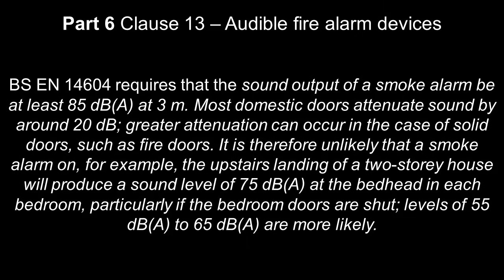That's the requirement. Most domestic doors attenuate sound by around 20 dB. Greater attenuation can occur in the case of solid doors such as fire doors. It is therefore unlikely that a smoke alarm on, for example, the upstairs landing of a 2-storey house will produce a sound level of 75 dB at the bedhead in each bedroom, particularly if the bedroom doors are shut. Levels of 55 dB to 65 dB are more likely.